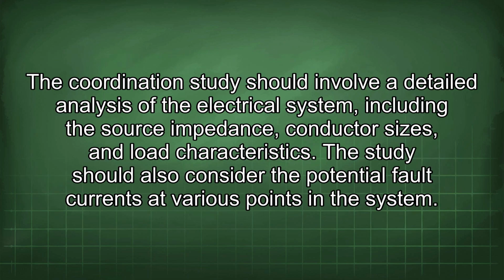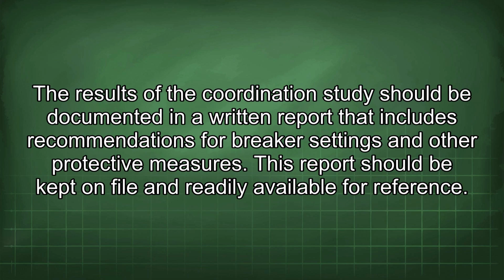The coordination study should involve a detailed analysis of the electrical system, including the source impedance, conductor sizes, and load characteristics. The study should also consider the potential fault currents at various points in the system. The results of the coordination study should be documented in a written report that includes recommendations for breaker settings and other protective measures. This report should be kept on file and readily available for reference.